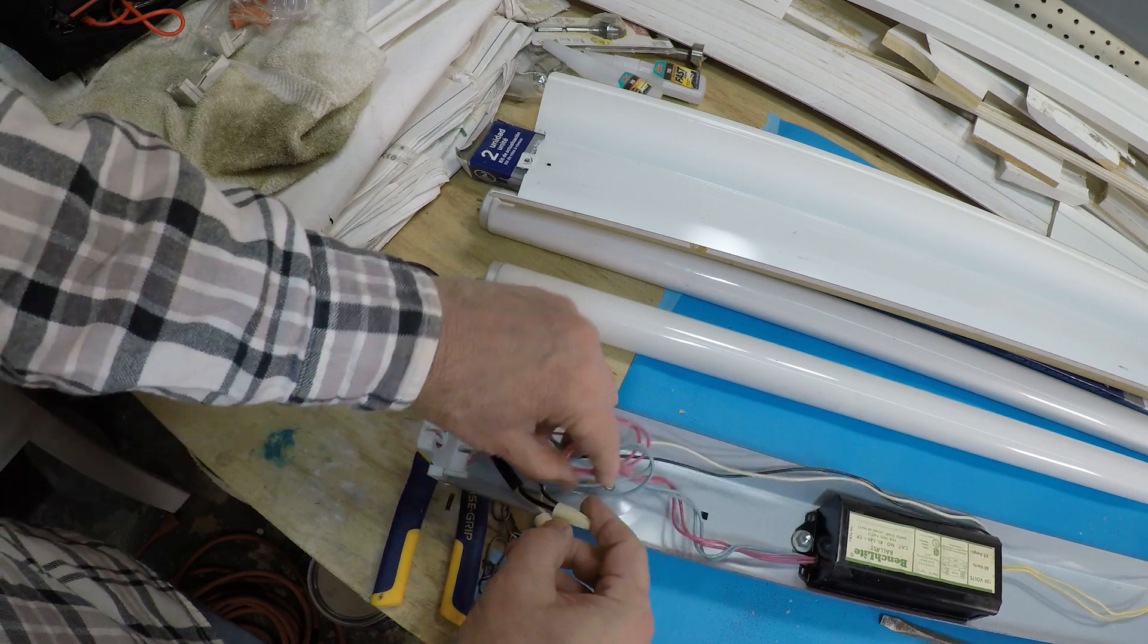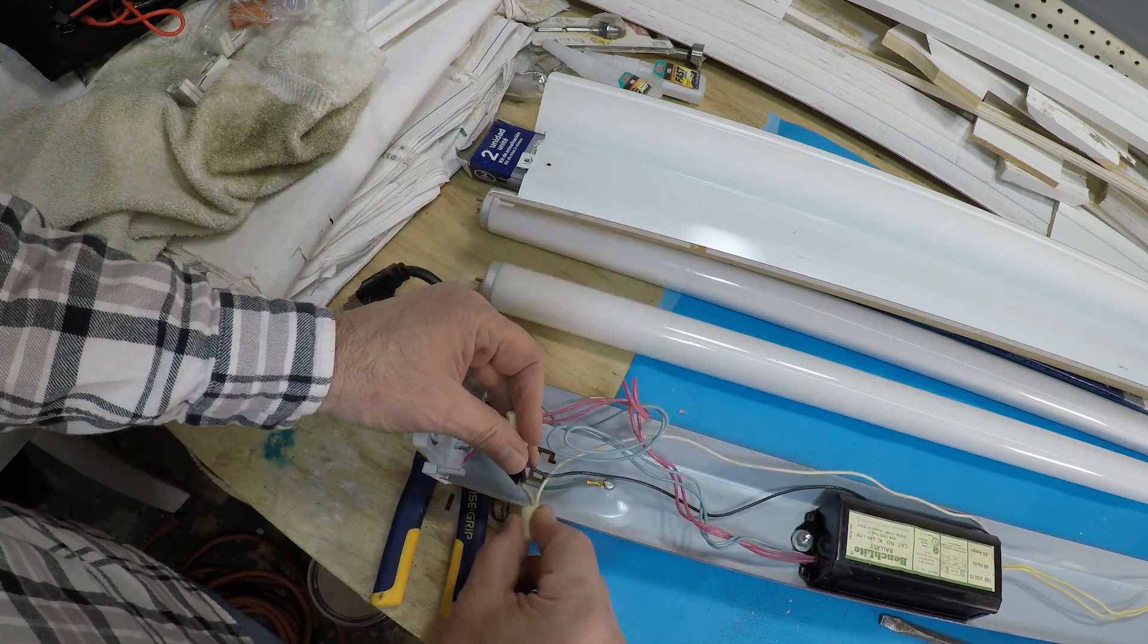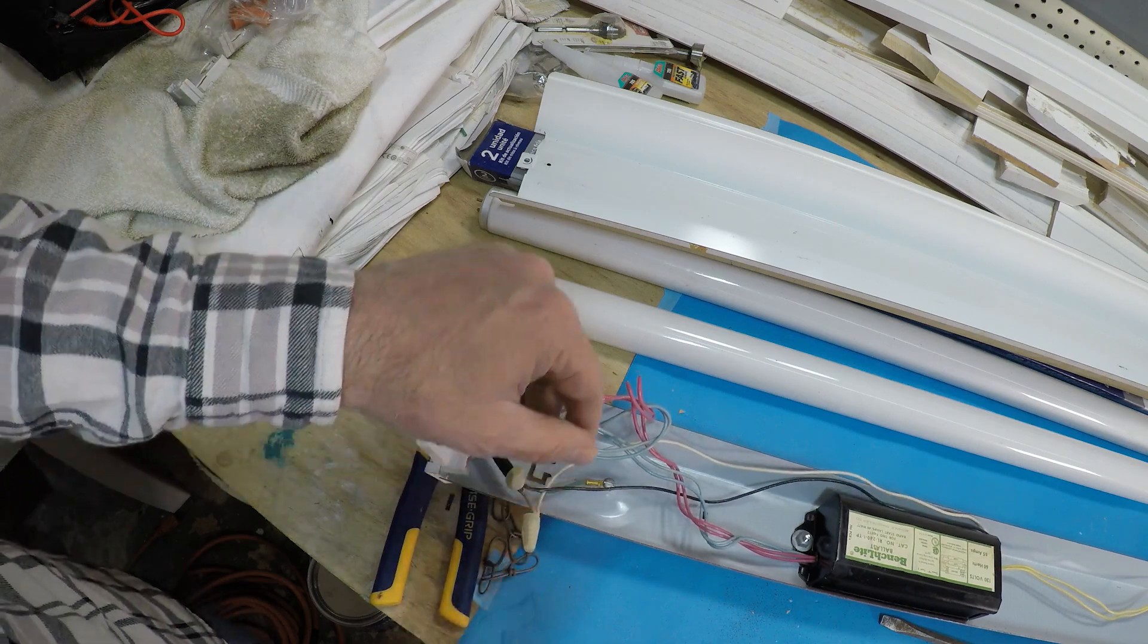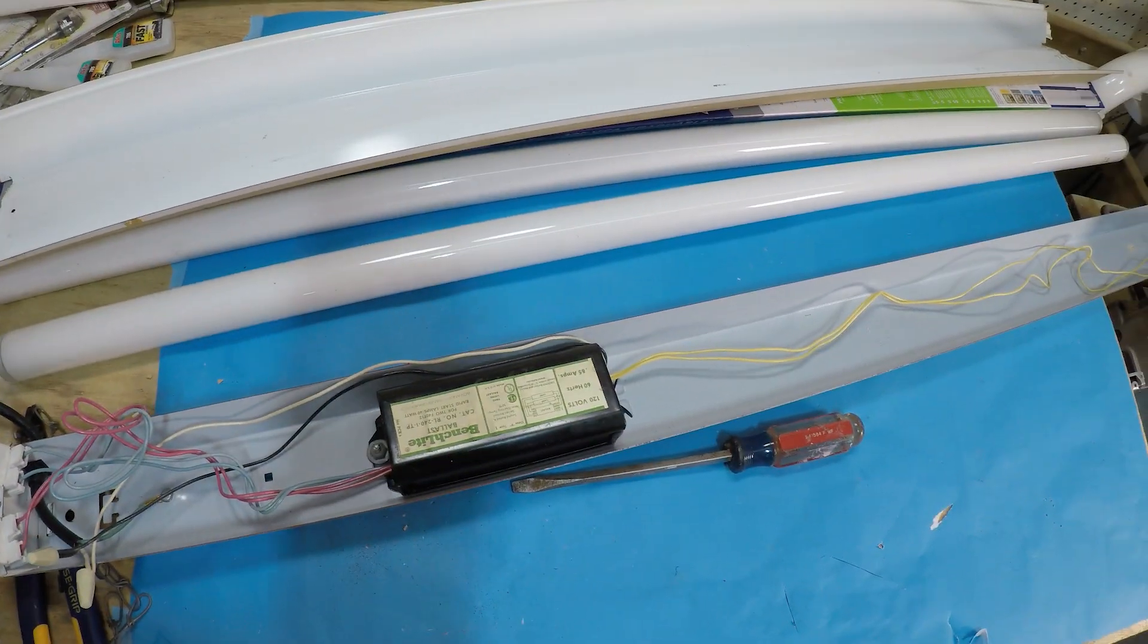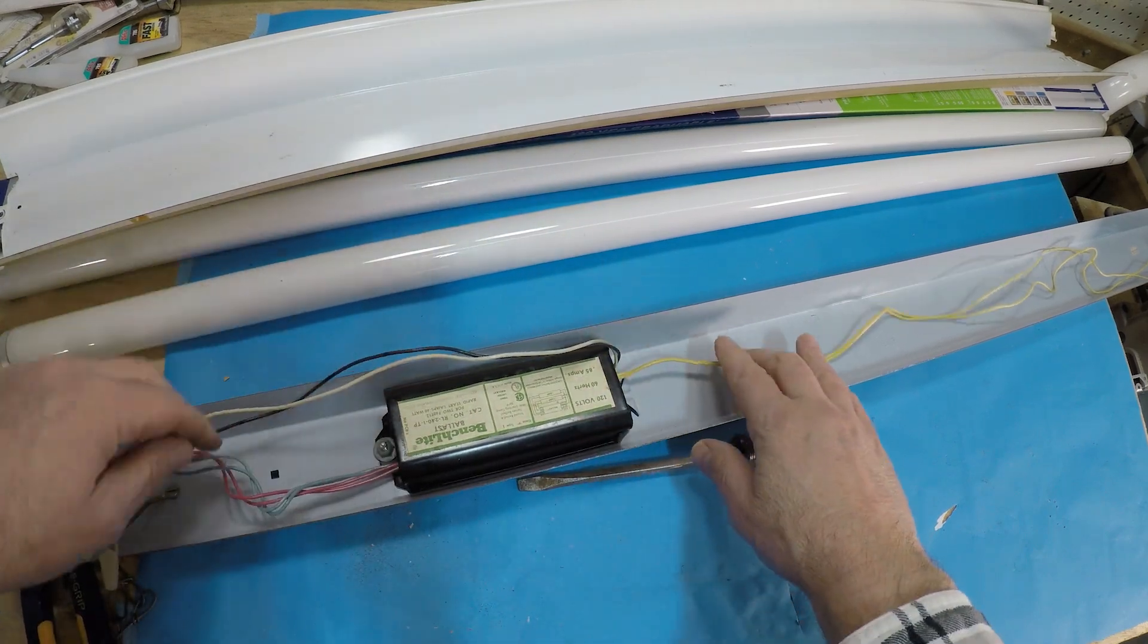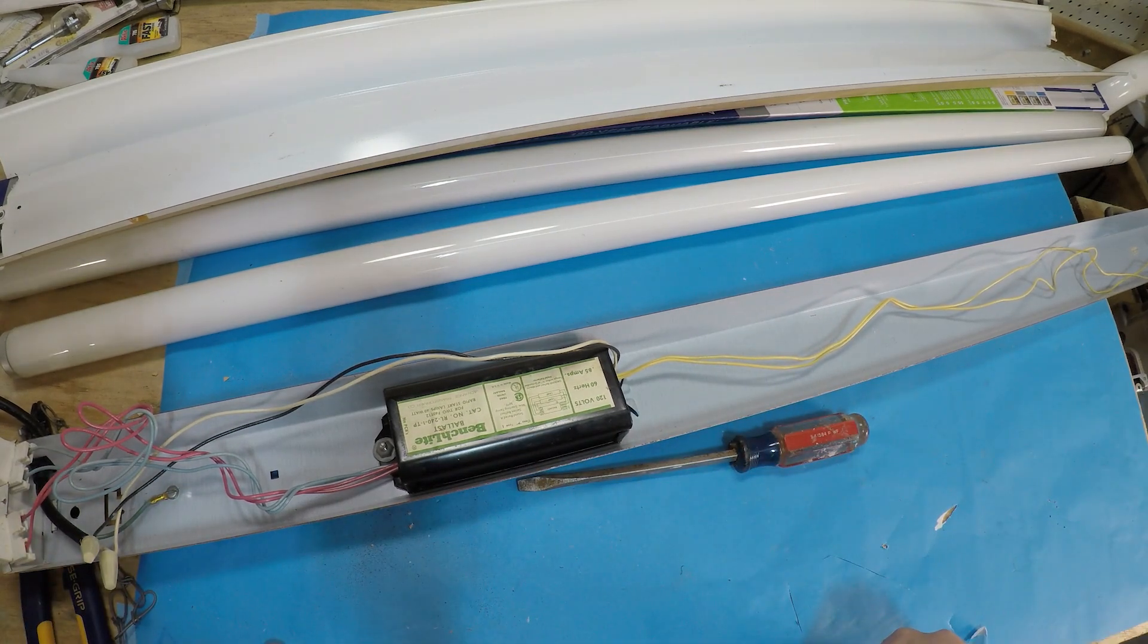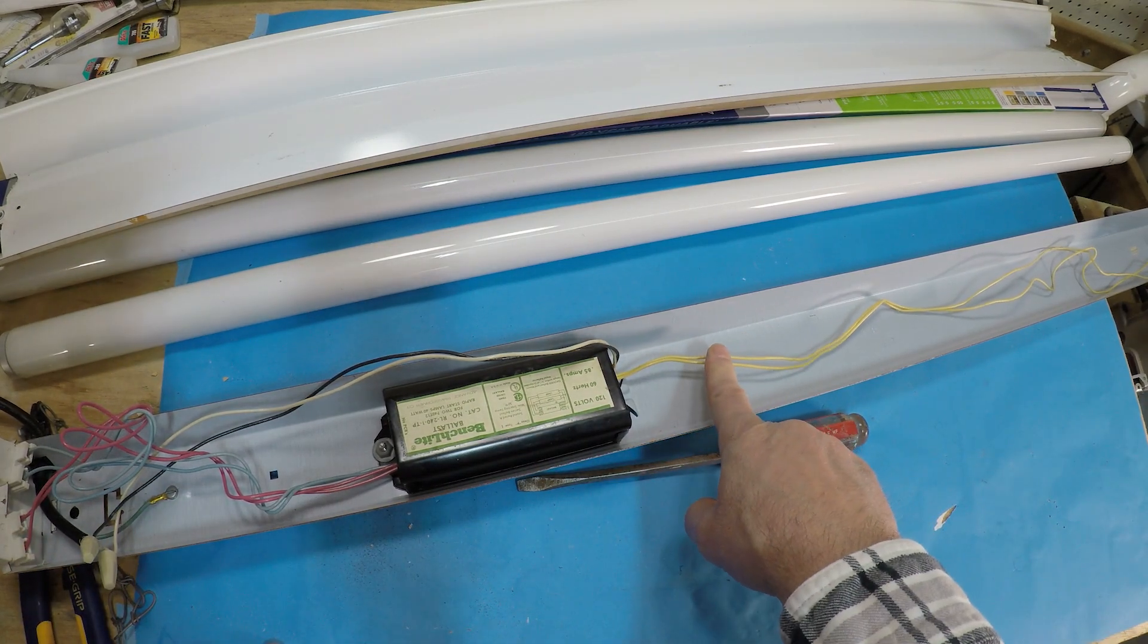And you've got your black, which is your hot, and your white, which is your neutral, going over to the one side of the ballast. And then you've got these other colors here that are going to the left side and the right side, which we're going to cut these off as well.